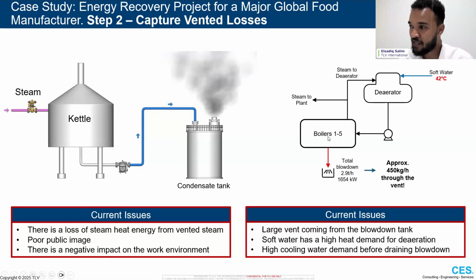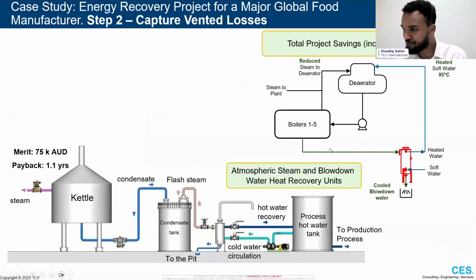And the second case is where we have boilers and their blowdown systems losing a lot of heat. So in this case, this is the one in New Zealand. They've got about 450 kilograms of flash steam being lost from their blowdown water, not to mention the very hot blowdown water as well going down to drain, which they need to cool down before they can send it down into drain for legal reasons. Overall, the blowdown situation, you can recover that blowdown heat with a heat exchanger, atmospheric heat exchange, and I'll explain why it's very important it's atmospheric in a minute.